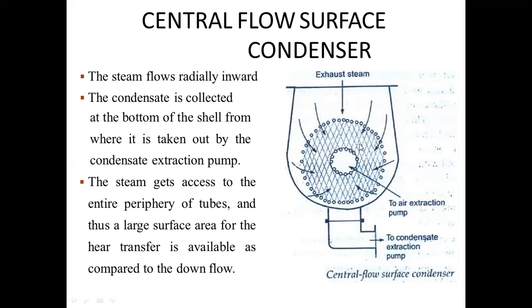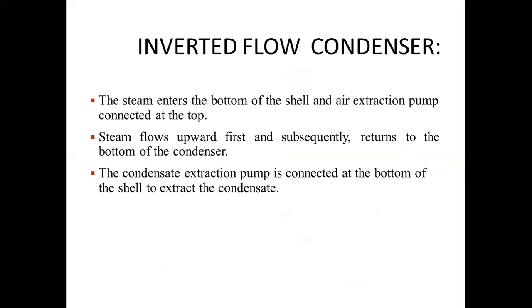When it comes in contact with the pipe, it releases its heat and steam converts into water, and that water is collected at the bottom, which can be removed with the help of a condensate extraction pump. And in the center of the condenser there is an air extraction pump which removes the air. The steam gets access to the entire periphery of the tubes, and thus a large surface area of heat transfer is available as compared to downflow.